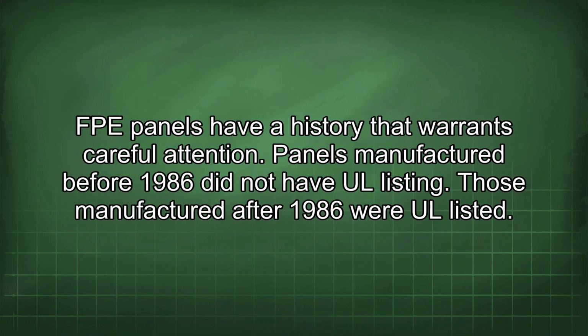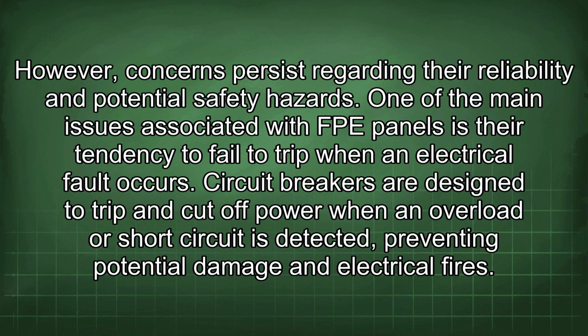FPE panels have a history that warrants careful attention. Panels manufactured before 1986 did not have UL listing. Those manufactured after 1986 were UL listed. However, concerns persist regarding their reliability and potential safety hazards. One of the main issues associated with FPE panels is their tendency to fail to trip when an electrical fault occurs. Circuit breakers are designed to trip and cut off power when an overload or short circuit is detected, preventing potential damage and electrical fires.